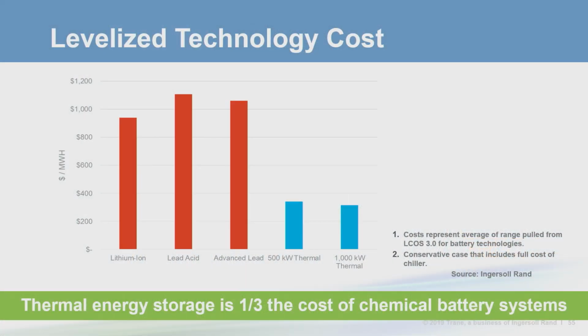This is a graph representing the levelized cost of storage. It compares the lifetime cost of chemical batteries to the lifetime cost of thermal energy storage with regards to the cost to store 1 megawatt hour. The costs for batteries are the average range obtained from the levelized cost of storage version 3.0. The cost for thermal storage is the conservative case that includes the cost of the storage and the chilling equipment obtained from Ingersoll Rand. From the graphs, you can see that thermal energy storage is around a third of the cost of a chemical battery system.